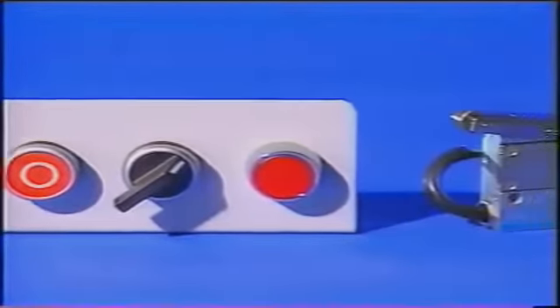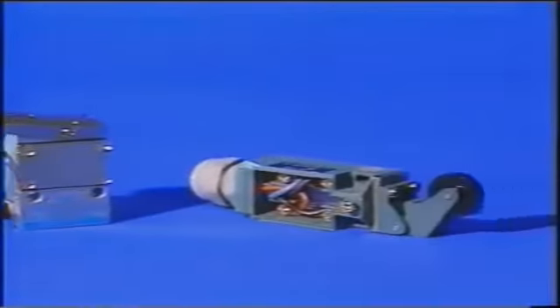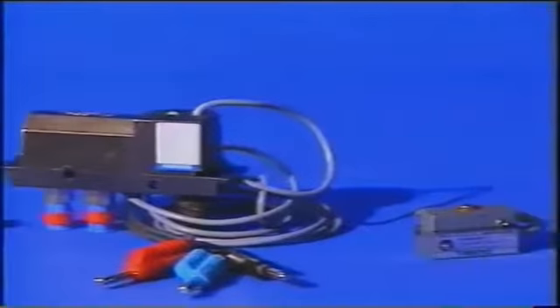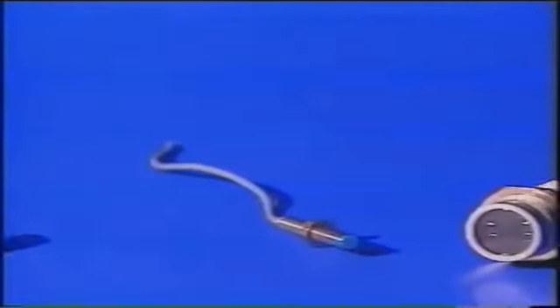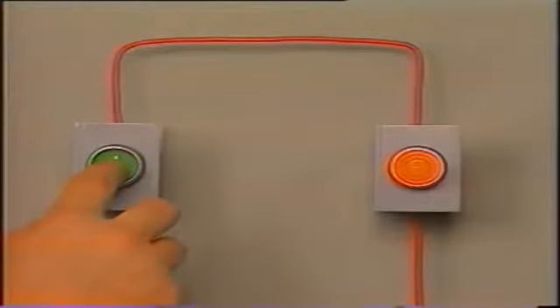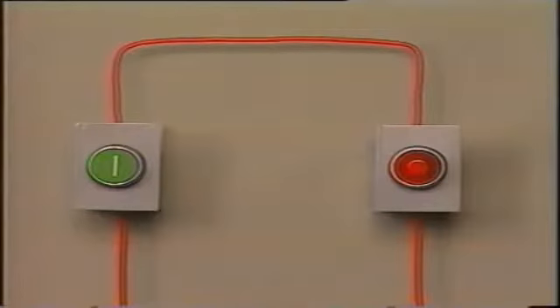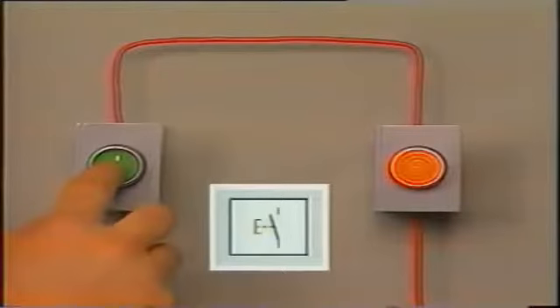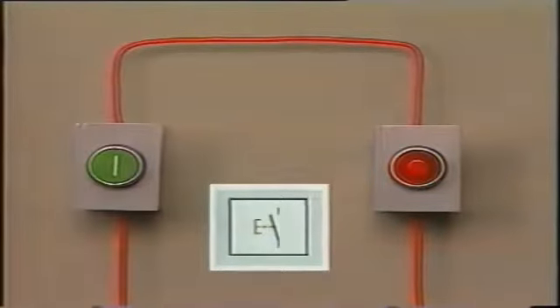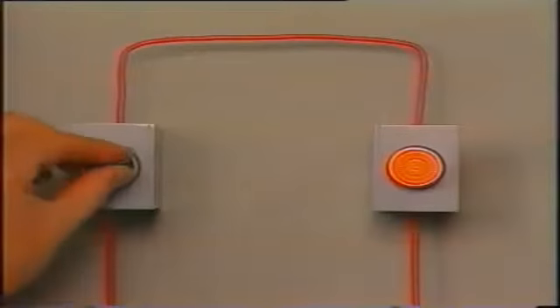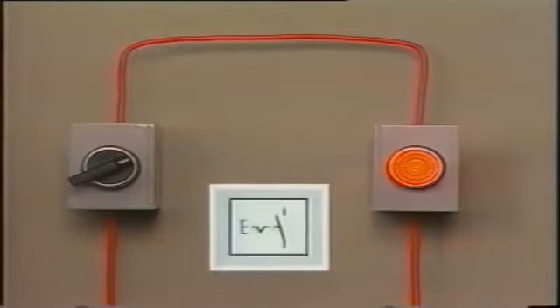The many different types of actuation for switches give some idea of the wide range of signals they can generate. Let's look at a normally open contact as an example. First, manual actuation. The contact only stays closed as long as the button is pressed. This is a push button, and this is the symbol for it. If the contact remains closed, it is a switch. This is shown in the symbol by a detent. The contact does not break until the switch is actuated again.